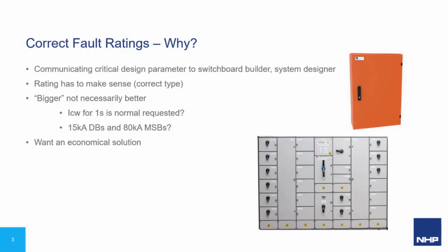So why are we interested in learning about fault ratings for assemblies? Communicating a fault rating is a critical design parameter to a switchboard builder, system designer, and ultimately the end user. The ratings we ask for and offer have to make sense for the type of components within the board. There is a common trend to ask for a bigger fault rating than what would be necessary. This can lead to something that you intended to be a panel board or a load center ending up looking more like a main switchboard.